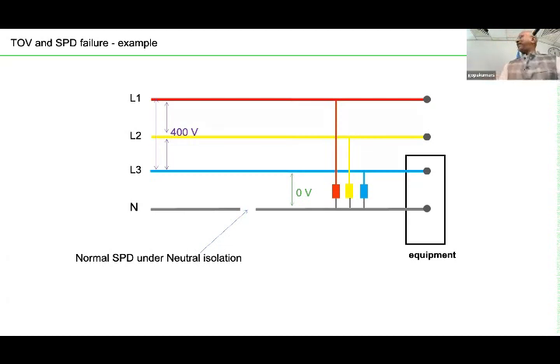So you have a single-phase equipment which is in on condition. So the potential between those 2 lines, line and neutral, is 0. The potential of neutral to the other 2 lines is now 400 volt. And how much time will it take to rectify this defect, which is the neutral isolation? How much time will it take?